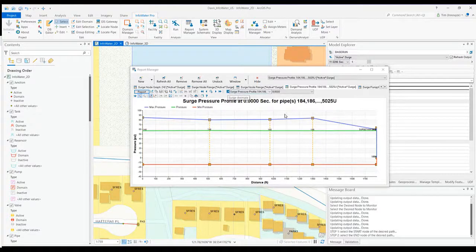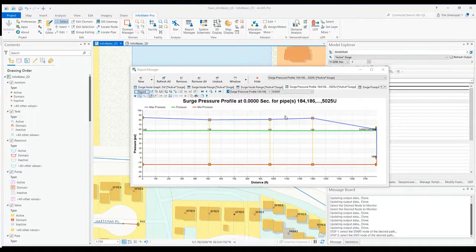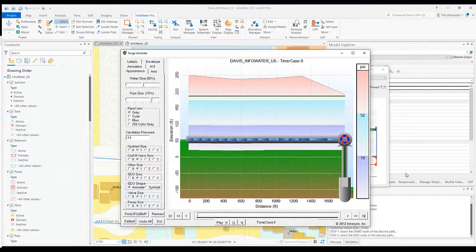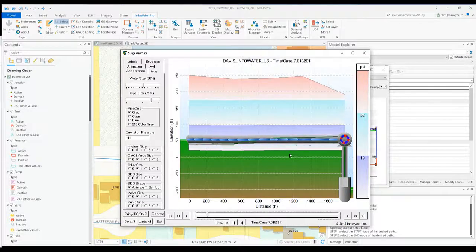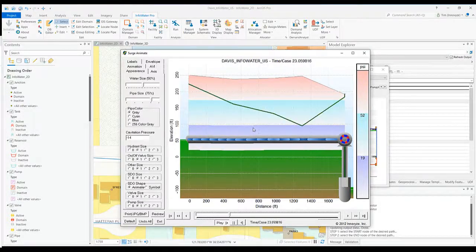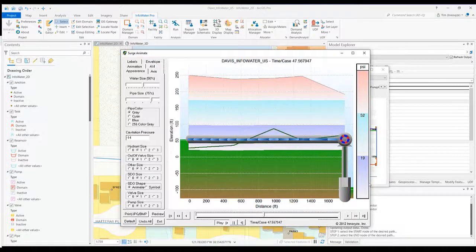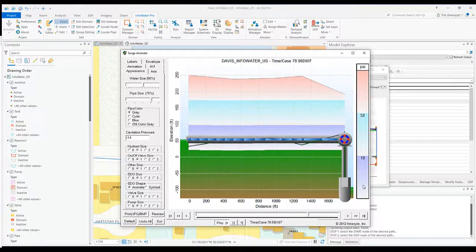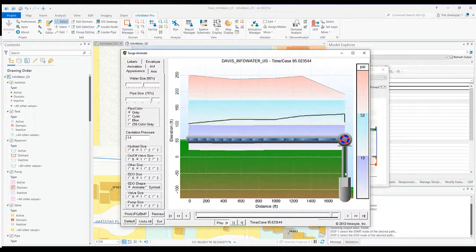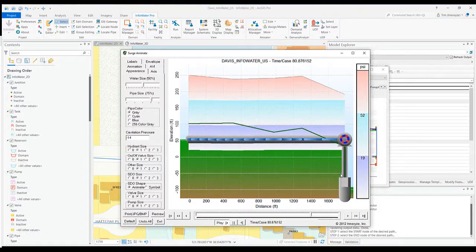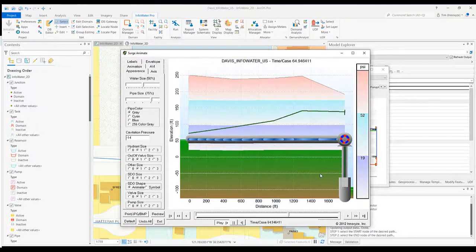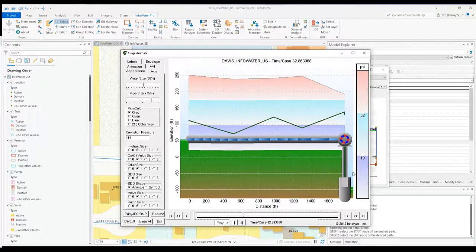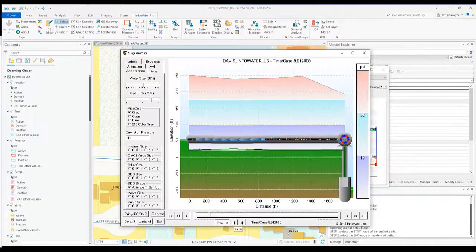Then I can look at that through a quick animation where we can start to look at the cavitation. If I play this, you can see the fluctuation, the change in pressure from this event, going very low, going very high. You can see the max, the min levels. The cavitation is popping up wherever you see the bubbles. The water is good here, but if you see the black, that's the cavitation being shown.